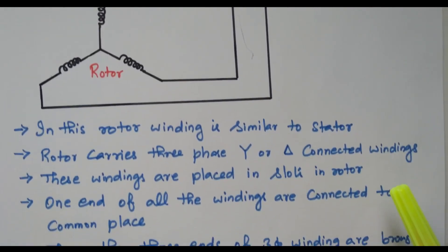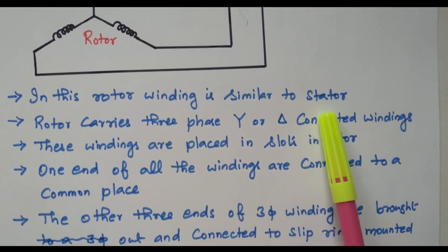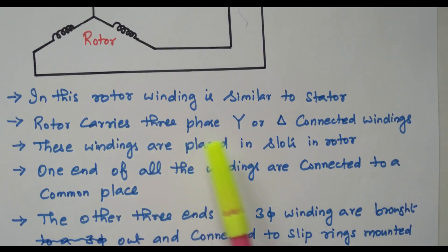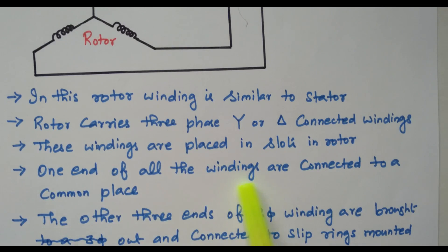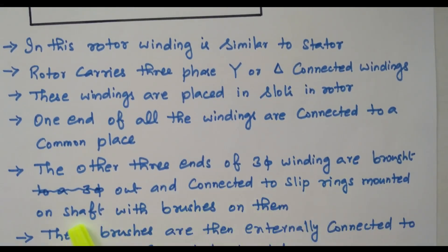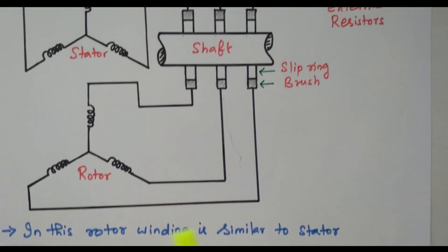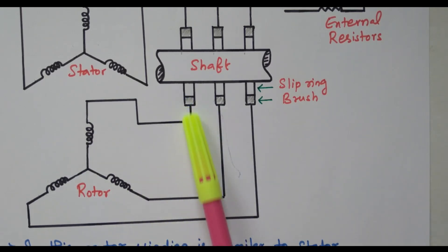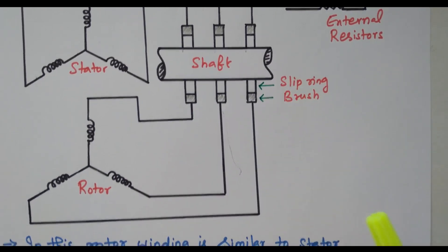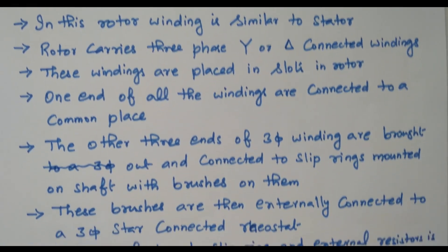Now we will see the description of the slip ring rotor. The rotor winding is similar to the stator winding. The rotor carries a three-phase star or delta connected winding placed in slots. One end of all three-phase windings is connected to a common point. The other ends of the three-phase windings are brought out and connected to slip rings mounted on the shaft with brushes on them. So one end is connected commonly, and the other end is connected through the slip rings and brushes.